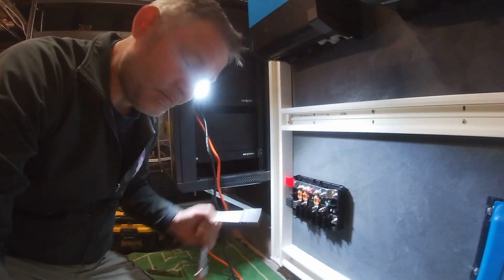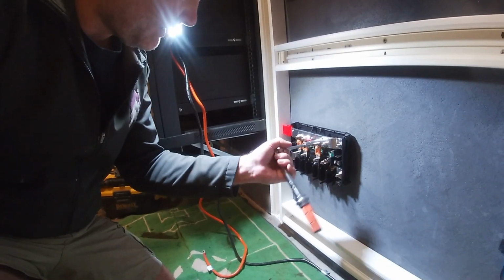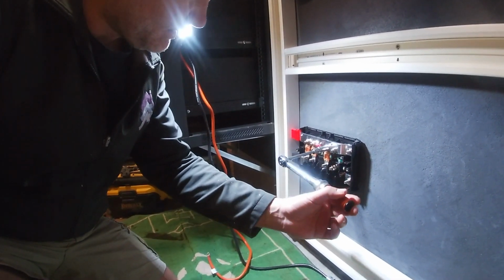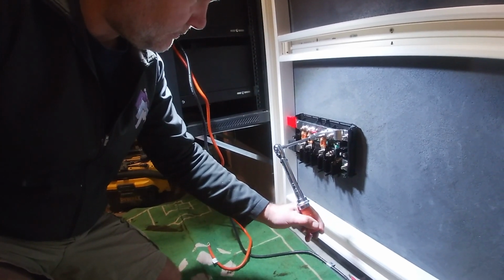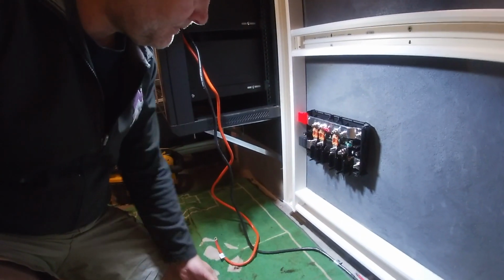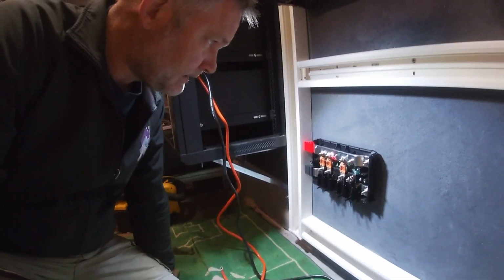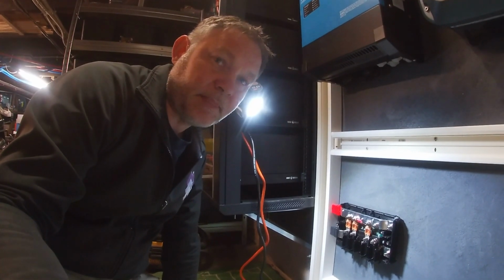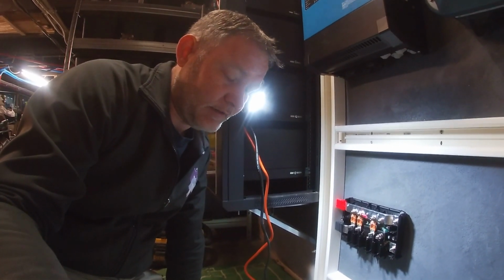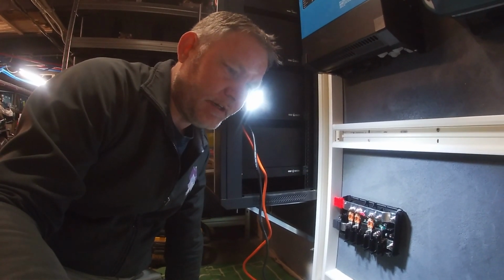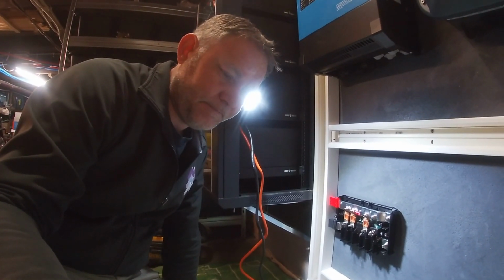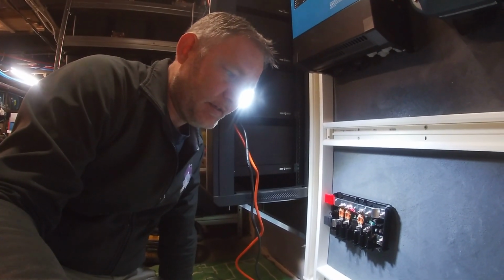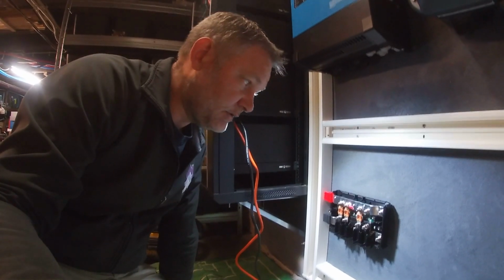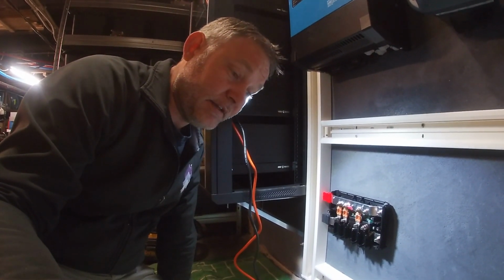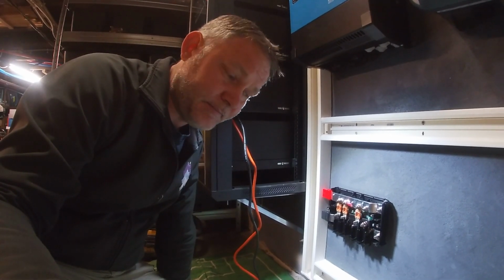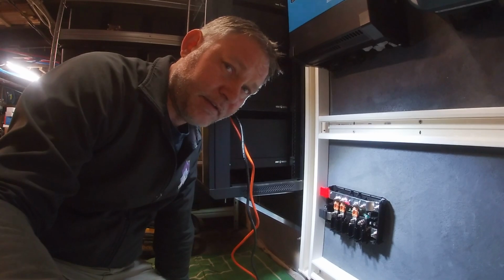Moving on. So then you use a mini torque wrench set to the required tightness, like that, and you know these are set at the required tightness. And we're going to be doing that a lot on this system, especially with the DC connections. The reason for that is loose connections are the worst, or the biggest enemy of these kind of systems. There's a lot of current being passed between cables and bars and devices, and if that connection is loose, it increases the resistance, heats up, and eventually sets on fire.